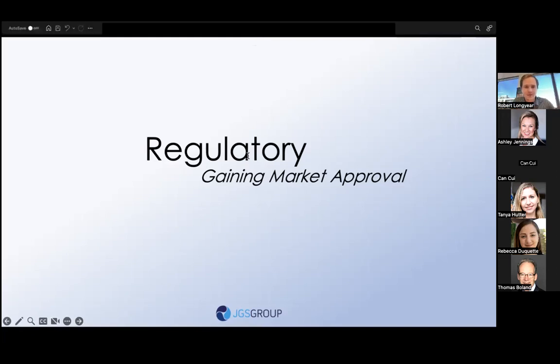Class 2 510K that does not require a clinical trial, do we still need to have the sample size discussion? No. If you're not doing a clinical trial, you may have to have some clinical validation that requires a certain sample size. But if you are not going through a 510K approach and it is exempt from a 510K, you're just going to register with the FDA, and there'll be some production controls required, as with anything that becomes registered or approved by the FDA. But if you're not doing a clinical study, then it'll probably be less relevant.